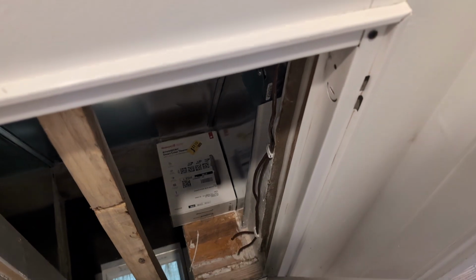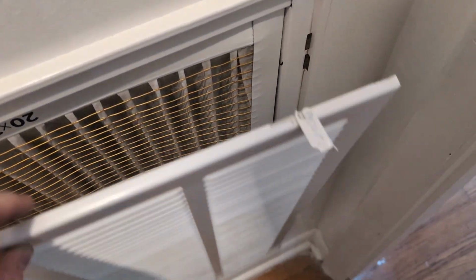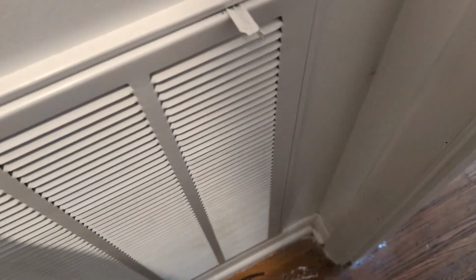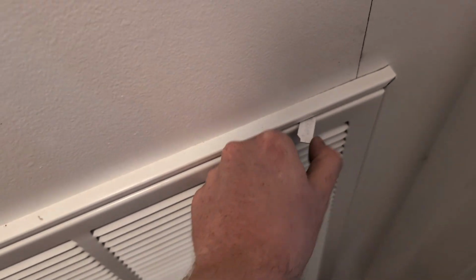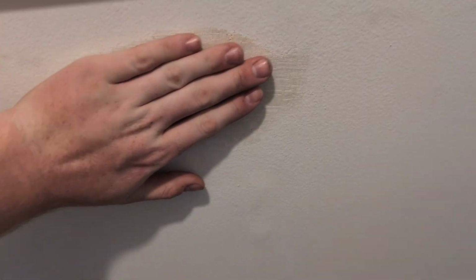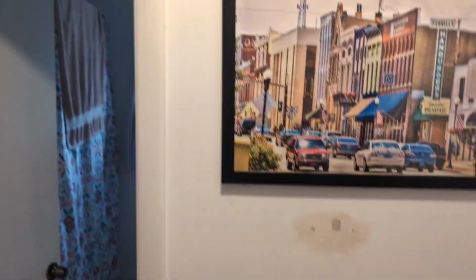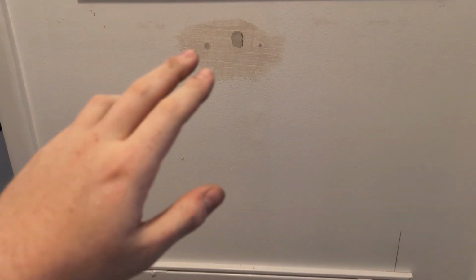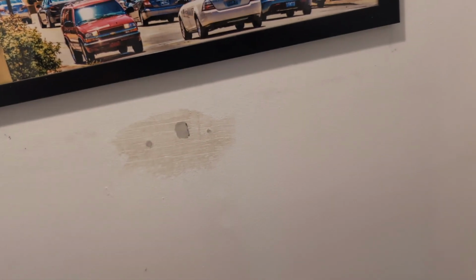You might notice there are 2 thermostat wires here. I need to change that filter. The reason for that, the thermostat used to be here, that's where I put it, I still need to sand and paint this. But if you look above, there's an attic hatch, and I didn't think about the fact that if the thermostat is here, the attic hatch is up here and not sealed perfectly, as you can see. The return's here, so air's going to go past it and cause it to read false.